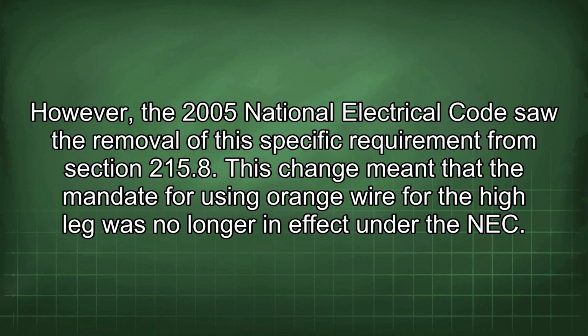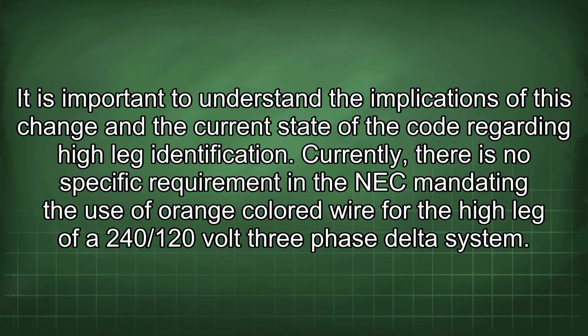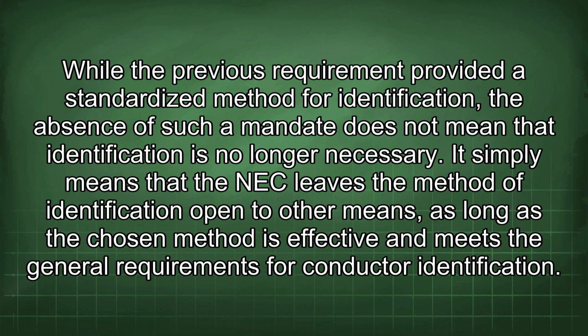This change meant that the mandate for using orange wire for the high leg was no longer in effect under the NEC. It is important to understand the implications of this change and the current state of the code regarding high leg identification. Currently, there is no specific requirement in the NEC mandating the use of orange-colored wire for the high leg of a 240/120-volt three-phase delta system. While the previous requirement provided a standardized method for identification, the absence of such a mandate does not mean that identification is no longer necessary. It simply means that the NEC leaves the method of identification open to other means as long as the chosen method is effective and meets the general requirements for conductor identification.